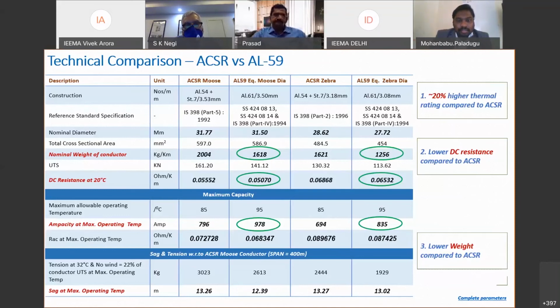Slide change. So the overall benefits, if you see, one is improvement in power transfer with reduced losses and improved reliability, which is high power transfer capacity compared to ACSR Moose. Just we have seen 20 to 25% higher power transfer capacity is available. Lower AC resistance even at the rated operating temperature. So the losses are lower, where you can save on the units generated and reduce the carbon emissions.